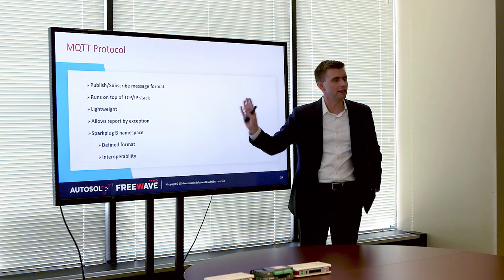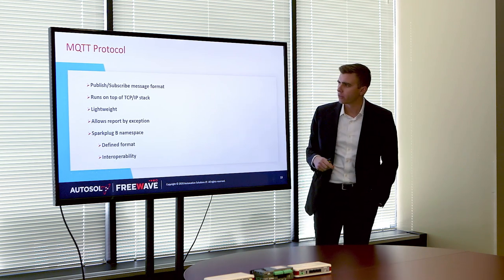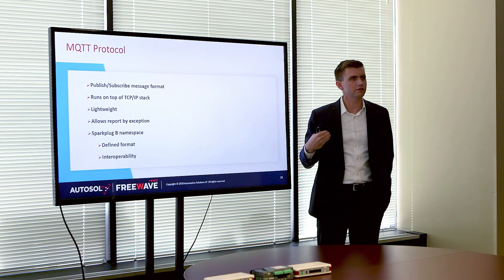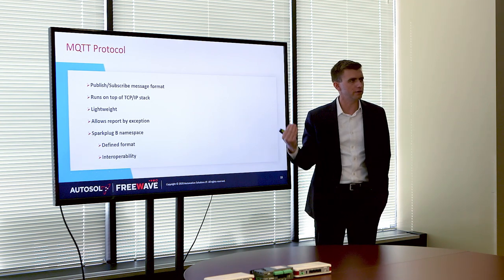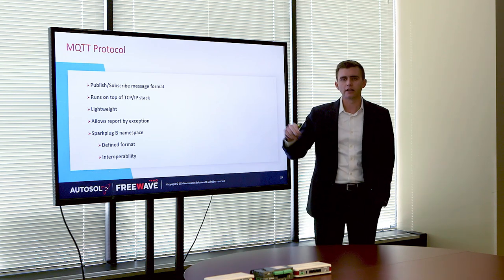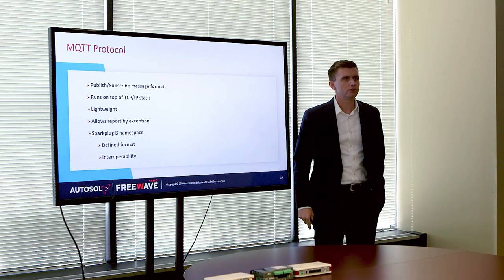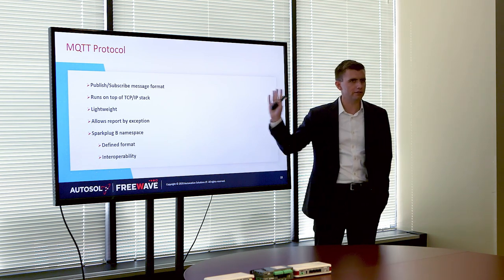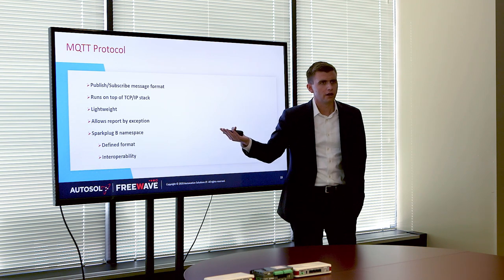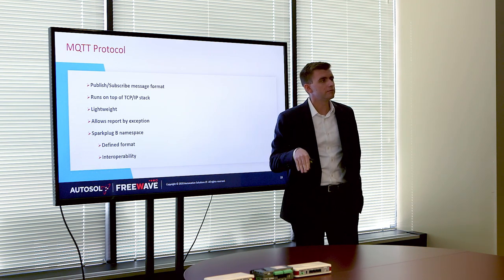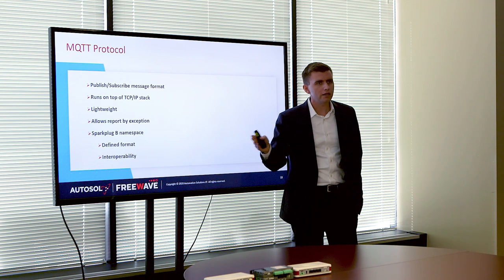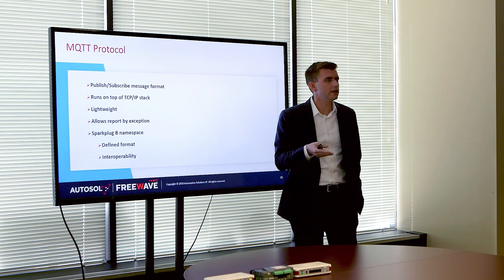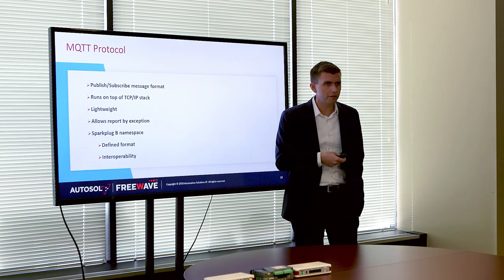MQTT runs on top of TCP/IP so you can inherit a lot of the security features from that. It's also very lightweight because it allows report by exception. With our poll-response scenario where I'm requesting 1,000 tags and really only 100 changed, with MQTT I would only send up 100 — not all 1,000. So I would immediately reduce the number of tags sent up by 900, seeing in theory a 90% reduction of bandwidth consumption.